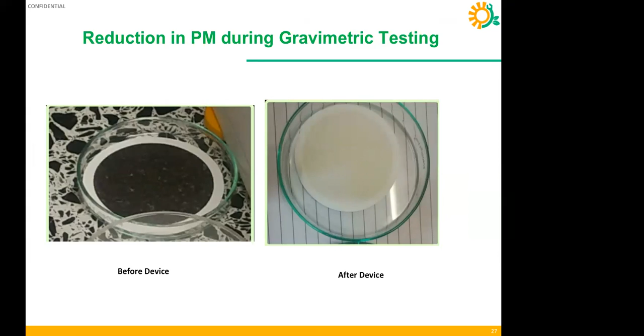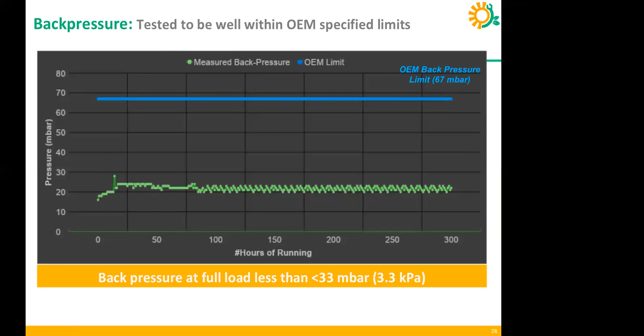This is the back pressure aspect I explained: even if the OEM limit is 7 to 10 kPa, my device functions at around 3.3 kPa. So you should consider 2 to 4 kPa to be the back pressure band that our device can achieve.